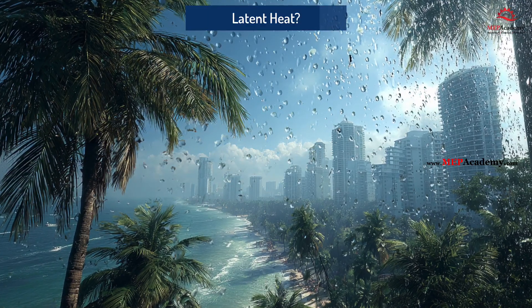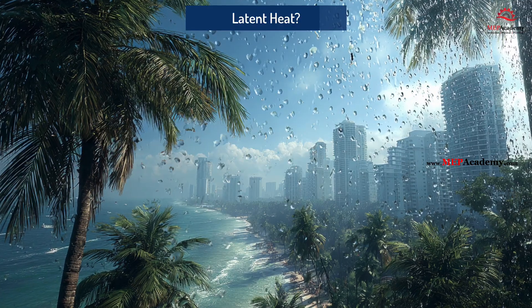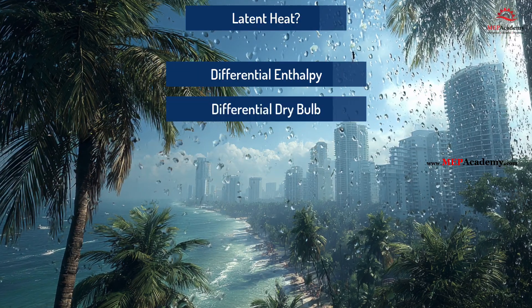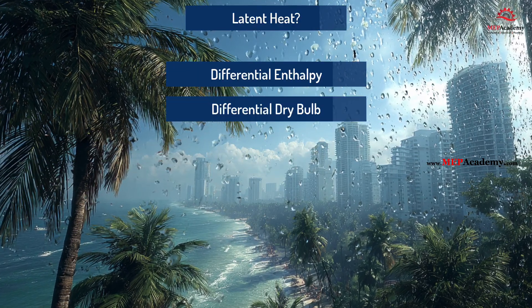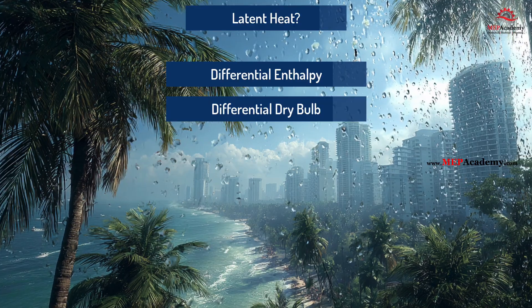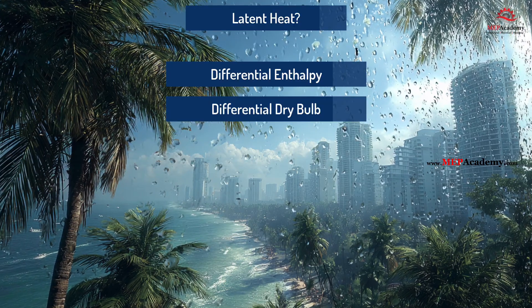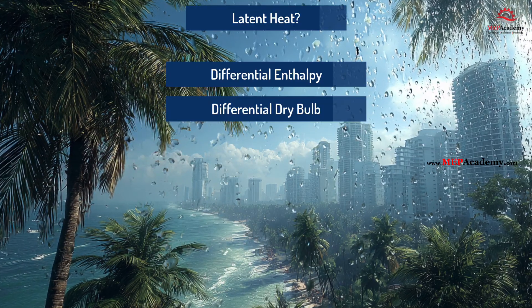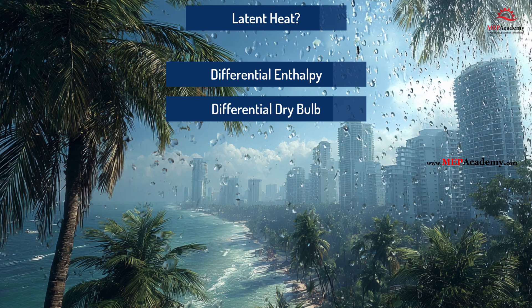In those cases, a more accurate approach is to use differential enthalpy and differential dry bulb control, which evaluates both sensible and latent energy. This ensures that economizer operation does not increase cooling energy use in humid conditions.